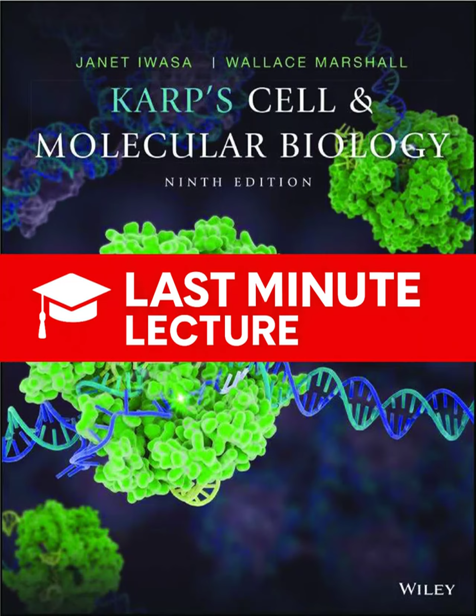That is the definition of empty magnification. The image size goes up, but the quality, the fine detail, actually gets worse because you've already exceeded the objective lens' ability to capture that detail. The quality of a scope is all about its resolving power. And there's a hard physical limit to this, governed by the physics of light itself, by diffraction.